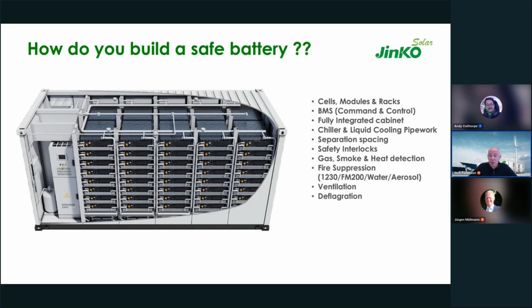So to build a safe battery, you start at the beginning. You choose the correct components - the cell choice is paramount. We choose LFP because of its safety record and robustness. We put those cells into modules and racks, and control and monitor them using our battery management system. We fully integrate that into the cabinet along with the cooling system, the gas, heat, and smoke detectors, fire suppression systems, ventilation, and personnel safety.